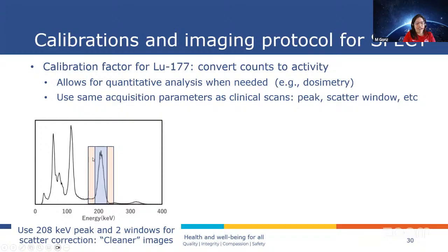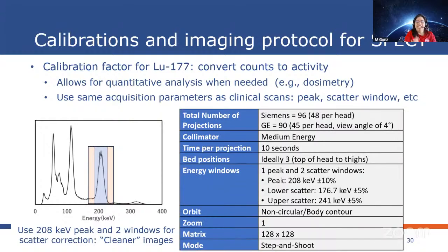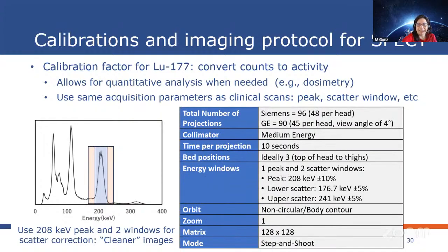So we can center the imaging window at 208, and we can have scatter windows around it, so that we can make an image of what the scatter looks like for a specific patient and use that for scatter correction. SPECT cameras can be programmed to image from this energy to this energy, with the scatter window from here to here. So we had to decide that. And the good thing is that once we decided, everybody in the province can start to do the same thing.